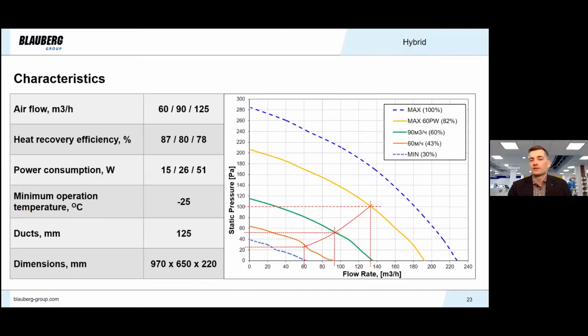We have adjusted speeds as shown on the diagram. Our target operation point for maximum speed is 125 cubic meters per hour at 100 Pascal. Minimum and medium speed were adjusted for 60 and 90 cubic meters per hour correspondingly. The enthalpy heat exchanger showed from 78 to 87% efficiency. As you can see, the power consumption is 51 watts or lower. Our goal was not to exceed 30 watts per fan so that we could sell the unit without bypass and still correspond to eco-design regulations.